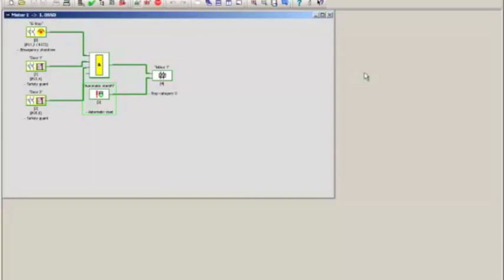So, let's go through some of the operations. Number one, I'm going to hit an e-stop and the machine will in fact turn off because the global AND function by virtue of receiving one false signal indicated by the red line and the red box around the e-stop goes to false. Therefore the motor will go to false and therefore the output will shut off. And that deactivates the motor contactor.